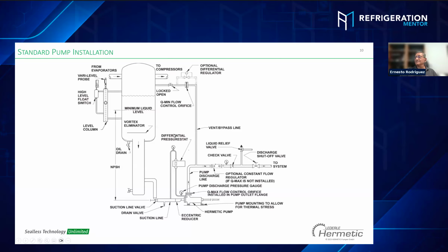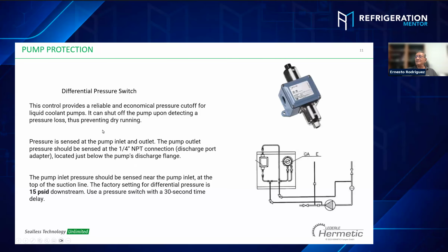What's the advantage of these accessories? Okay, the differential pressure switch. Most of the companies try to go to the basics. They don't want to have PLCs or controllers. They have a very simple system to control. The pressure stat is the best, cheapest way to protect the pump. When we have a very low differential pressure, the pressure stat immediately sends the signal and stops the pump when it starts cavitating from low pressure, or when it starts getting too high a differential pressure. In the same way, the pressure stat is going to send a signal to stop the pump.